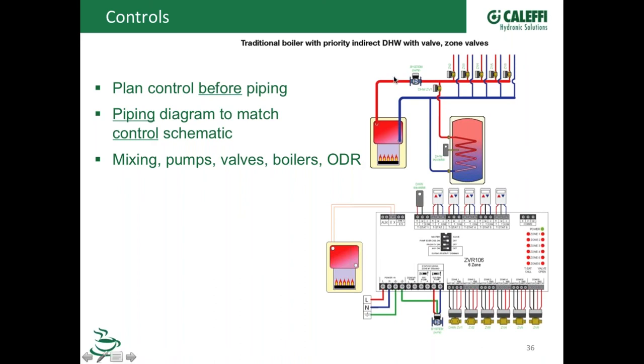I don't know of anybody else that has the piping, the wiring, and an essay that explains what's going on. Okay, when the thermostat calls for heat, the relay is going to come in, open the zone valve, and turn the pump on. You have the ability to put your secondary pump and your boiler pump on here. So we tell you in a paragraph or two what's going on and what to expect, then show you how to wire it and how the piping would match up with it. We've got these for pumps as well as zone valves. This one just shows a zone valve example.